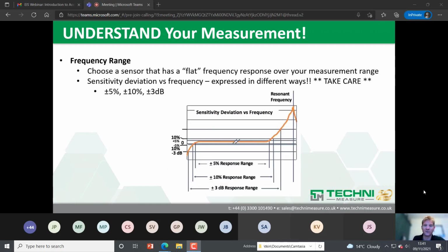You're looking to choose a sensor with a flat frequency response over the measurement range. The sensitivity deviation versus frequency on a data sheet will be expressed in different ways. Commonly, you'll see a 5% response range, which is a 5% sensitivity deviation from the nominal sensitivity. You can see that as it curls up on the right-hand side towards your resonant frequency, and curls down with the low frequency roll-off on the bottom end, a 5% response range is a very good reflection of the flat curve in the frequency response. 10% is another common thing you'll see on a data sheet. That will give you a slightly wider range.